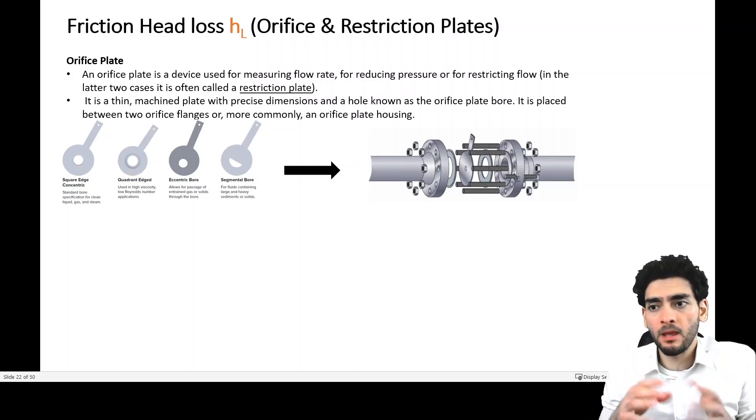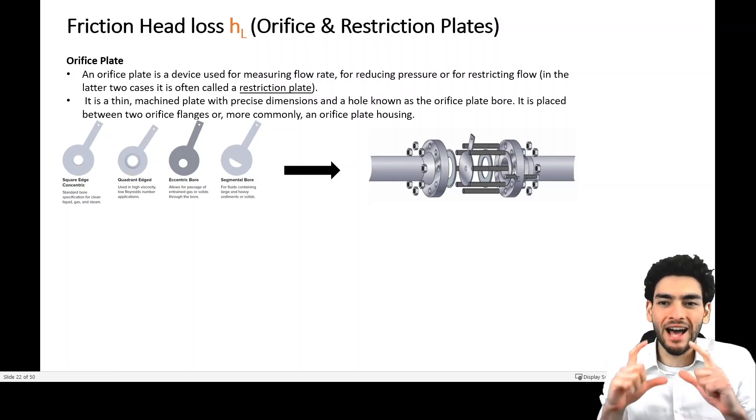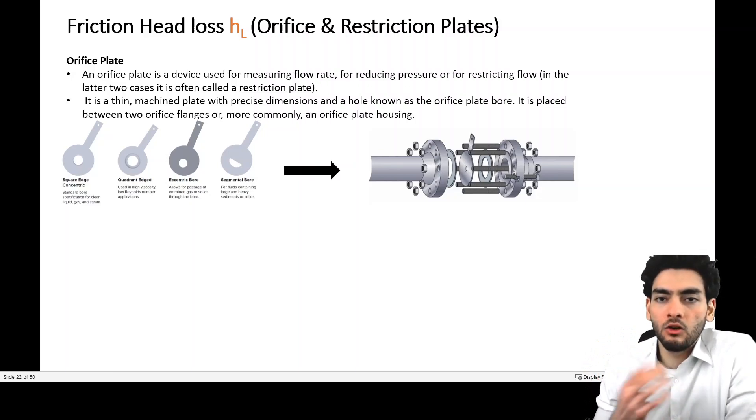An orifice plate can also be used for reducing pressure or restricting flow. In the latter two cases, we often call it a restriction plate. It's essentially a thin plate with precise dimensions and a hole inside that thin plate, known as the orifice plate bore.